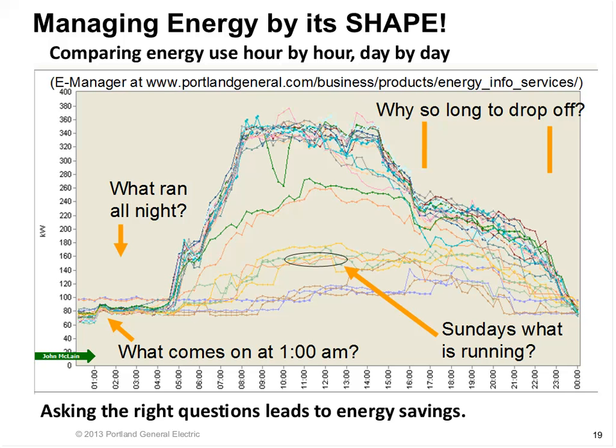And the boss said, well, how long does that take? And they said, well, it takes about 45 minutes. And the question was, well, why doesn't it then turn them off? And they said, well, we bought this really good deal on software. It knows how to turn them on. It doesn't know how to turn them off. So the facilities manager decided to pay for the extra special software that not only could turn the equipment on, but turn it off. So he changed the shape from this bump in the night to dropping it back down here, and saved all this energy by turning the equipment off.